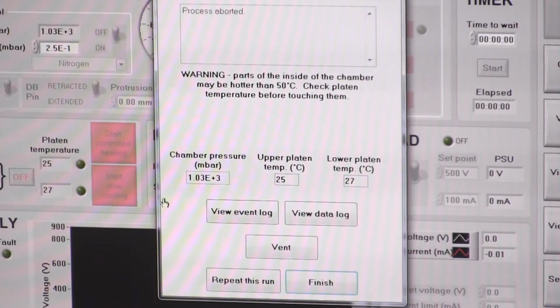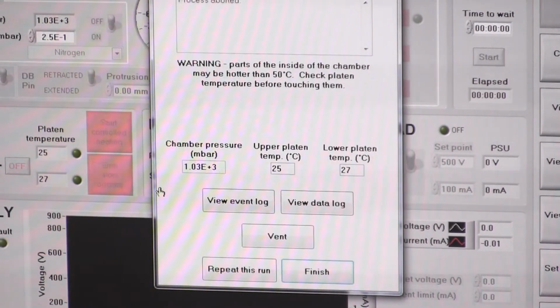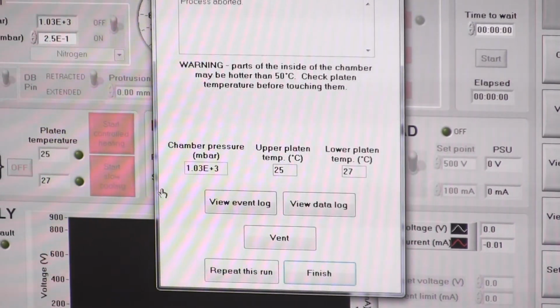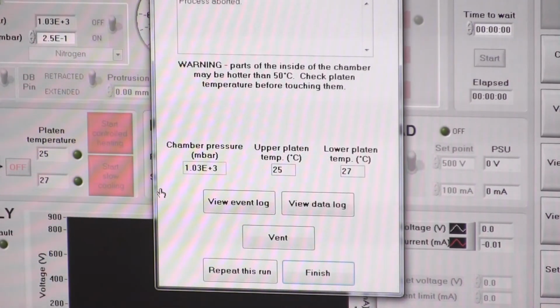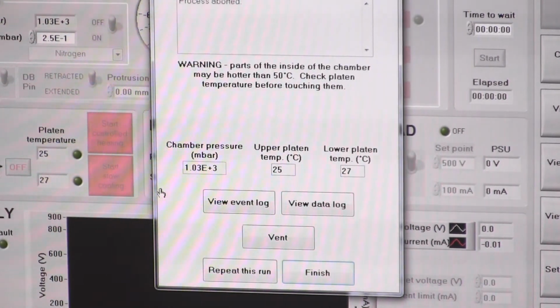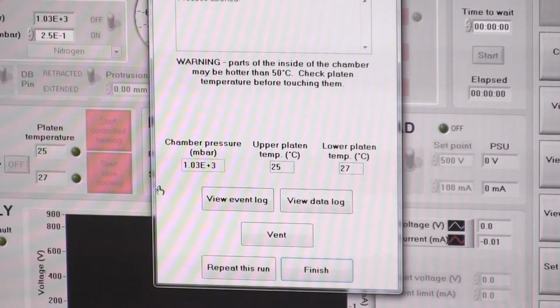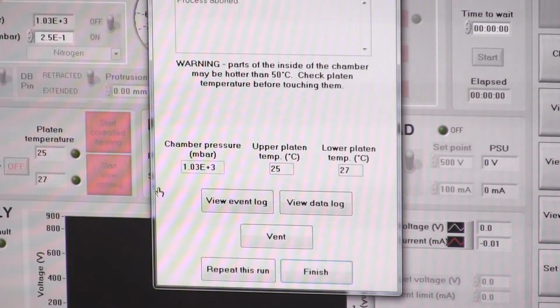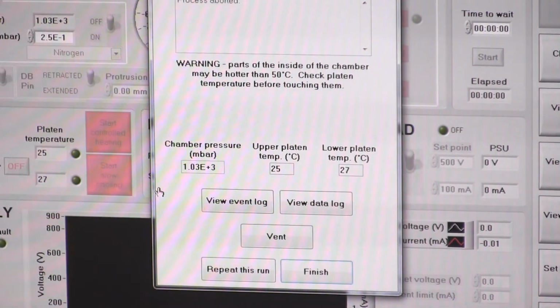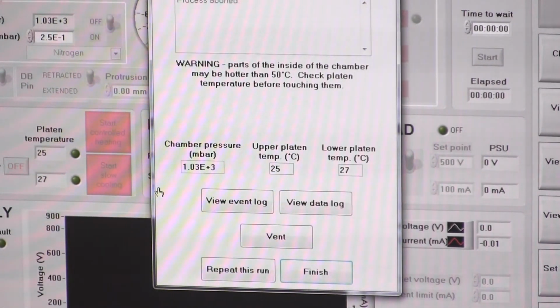It will not allow you to open the lid until the temperature is below 200 degrees. That's partly for your safety and partly to prevent oxidation of the internal components. So if there's oxygen in the chamber above 200 degrees, you risk oxidizing things inside, which can make wire connections brittle and just cause other problems generally.